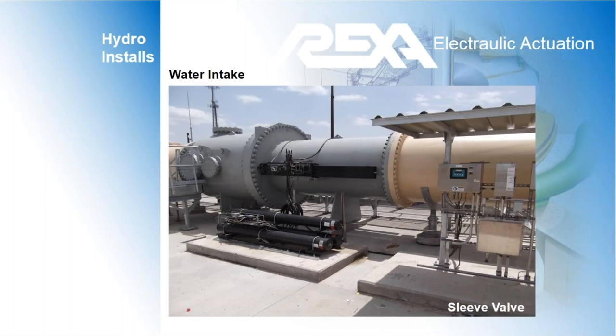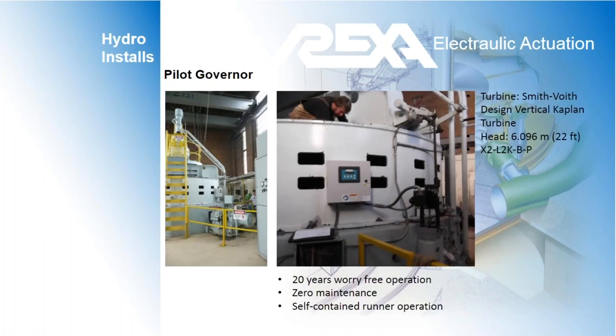This slide, we have a sleeve valve with fail-safe capabilities for water intake. And like the cooling water valves, this unit, sized at 2,000 pounds of linear force with a 2-inch stroke, were installed in the 90s as well. The unit in the picture operates a pilot valve to adjust the pitch of the Kaplan blades.